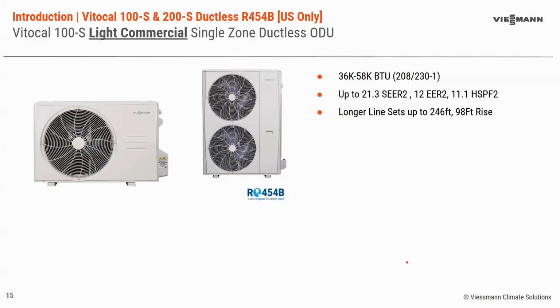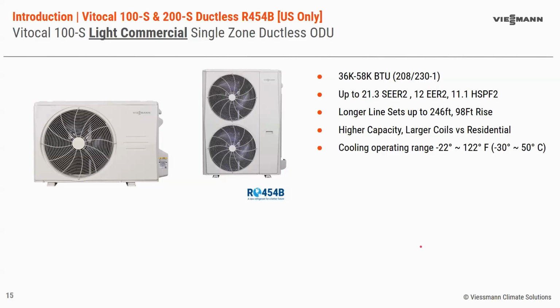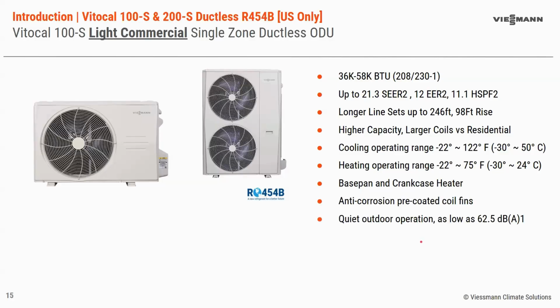So from indoor unit to outdoor unit, you can have up to 246 feet of line set and up to 98 feet of rise, so above or below the outdoor unit. You achieve higher capacity with these light commercial units. You get larger coils. The fans outdoors move more air for that higher capacity versus the residential applications. However, you're still getting that heating and cooling operating range down to -22 degrees Fahrenheit. Still get the base pan and crankcase heater, coated coils, quiet outdoor operation, refrigerant leak detection.